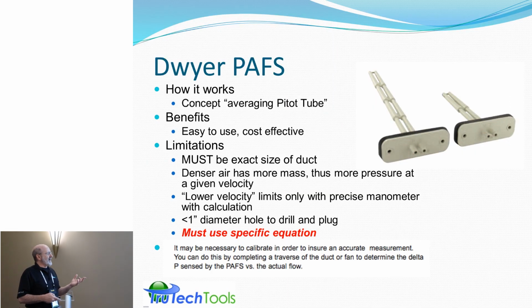Dwyer has what's called a plastic airflow sensor, similar type of concept, the averaging pitot tube. Must use the manufacturer's specific equation, which is an adaptation of that pitot tube equation. But one of the big factors here is, they even state it, you might need to calibrate it before you can use it in the duct you're using it in. Again, it's not meant to be a measuring device. It's meant to be calibrated to be a measuring device.